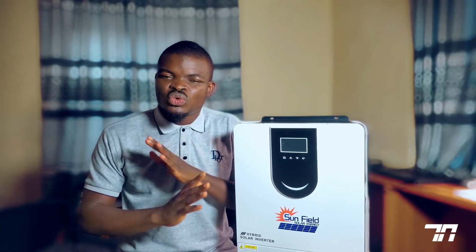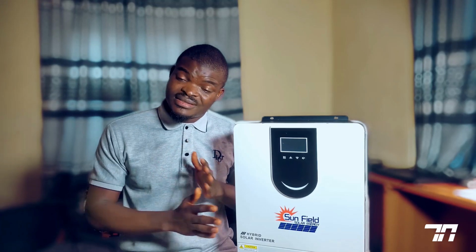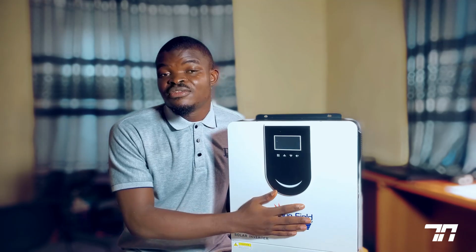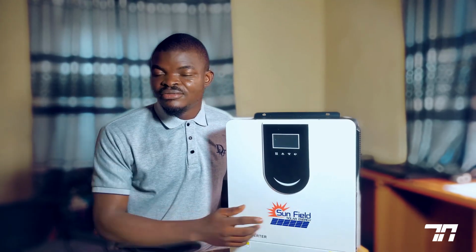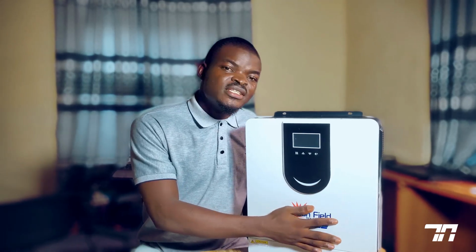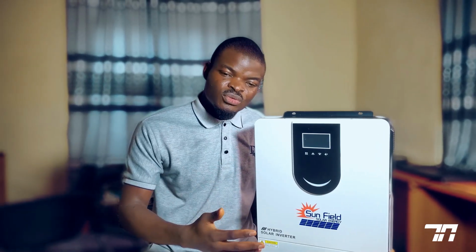And it will be totally okay. In fact, in the manual it's recommended 4 mm. You can use 4 mm to draw 8 pieces of panel in series for each string. High voltage that it is gives you the advantage to be able to use lower gauge of cable.